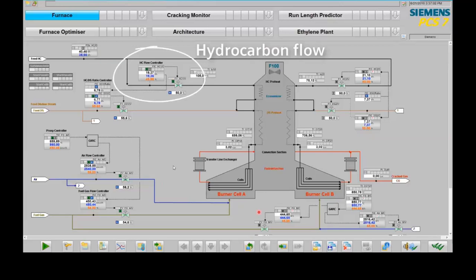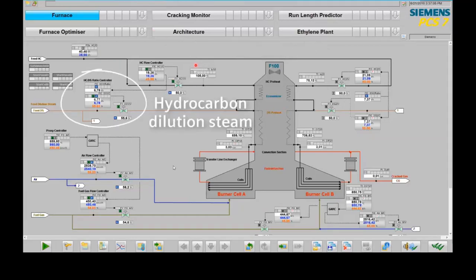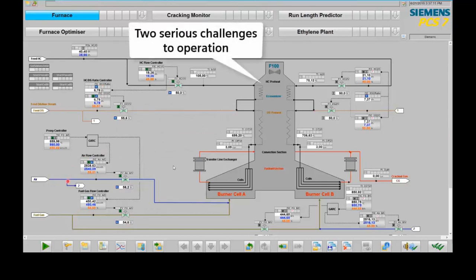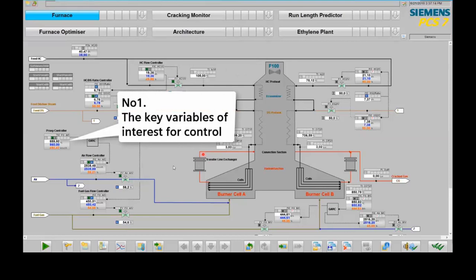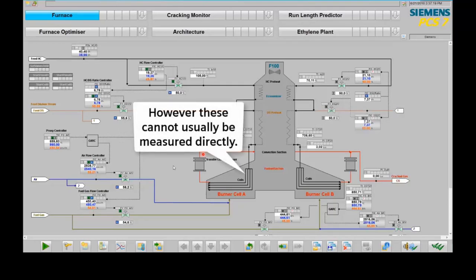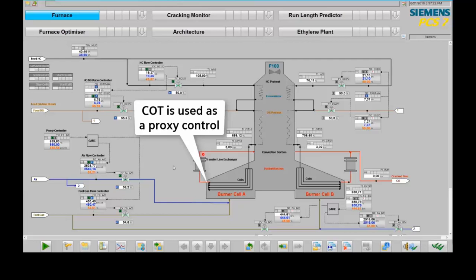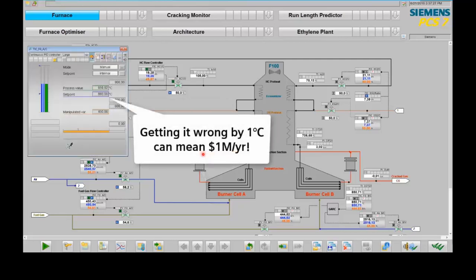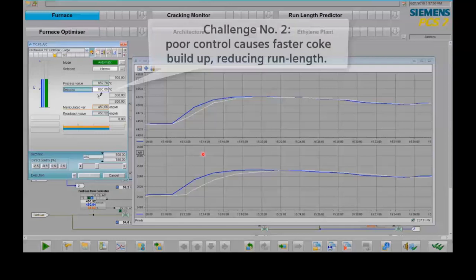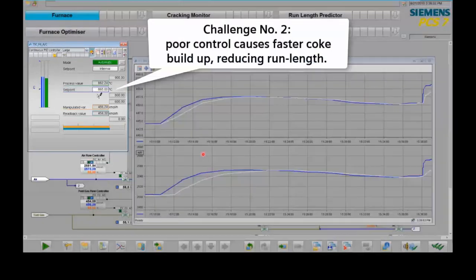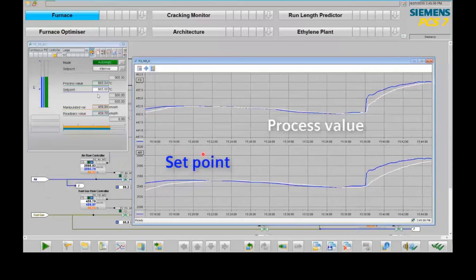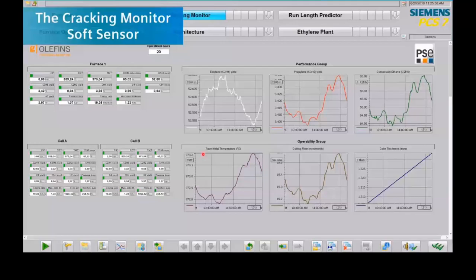Here you see a typical operator screen. In the middle is the furnace; you can see the hydrocarbon flow control, feed dilution steam control, and heat control. There are two key challenges. The key variable of interest is the temperature in the coils, which cannot be measured directly — so typically you use a proxy control. When you get it wrong and have a mismatch, this can lead to a loss of 1 million per year per degree of temperature mismatch. Poor control and the build-up of fouling or coking further increase production losses.